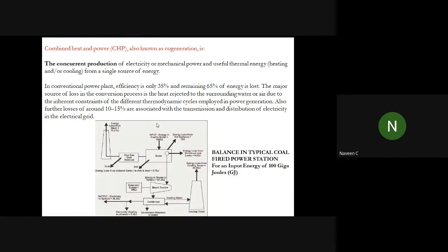Even if you are maintaining everything perfectly, the cycle efficiency itself is 40%. If you have other operational issues, there will be a severe drop in the efficiency. There are some power plants running at 22% or 20% efficiency in Tamil Nadu itself, due to investment requirements, initial project, land acquisition and other processes. We are still running at a low efficiency. But it is not advisable to run a power plant at 22% efficiency.